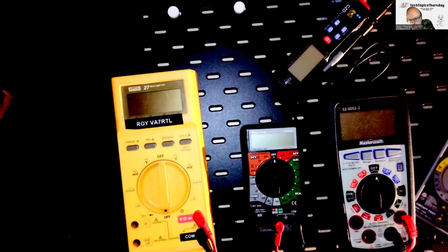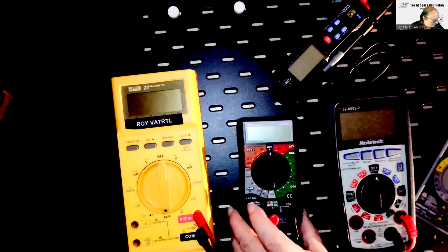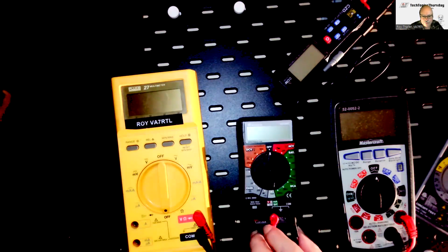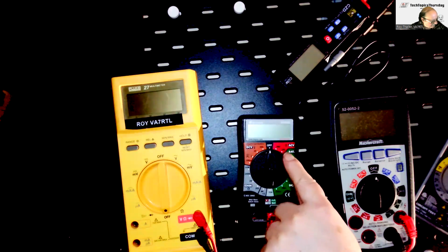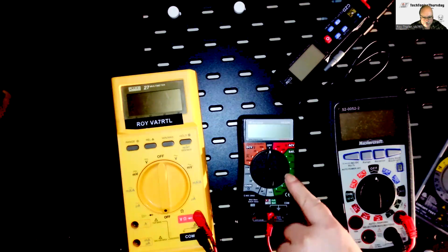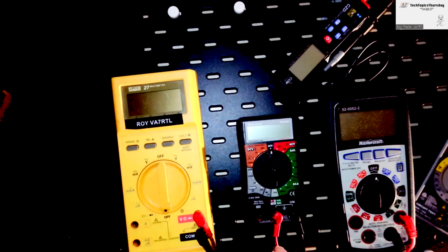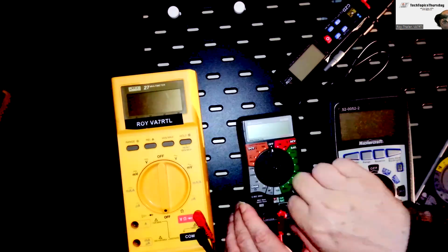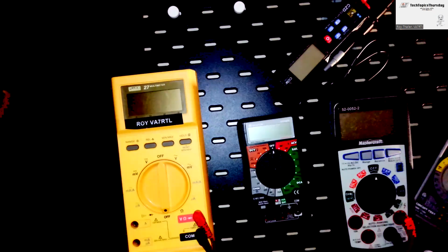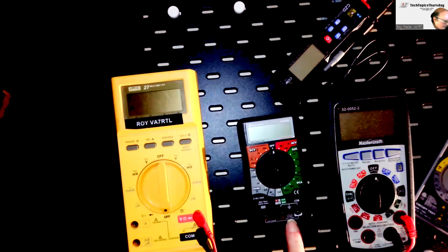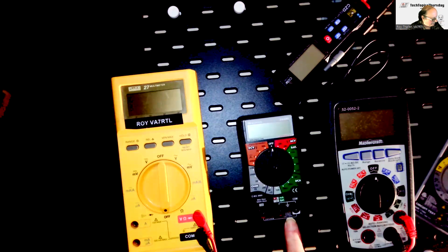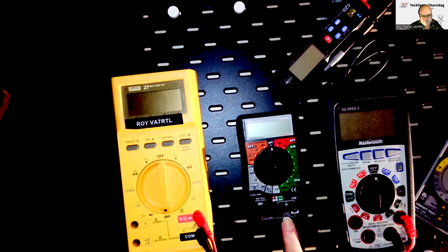This meter I got at Canadian Tire, probably because it has the battery scale here to measure batteries. But when I look at the rating, it says Cat 1, which is the least amount of protection, and 500 volts. So do I really want to use this meter at 500 volts if it's Cat 1 rating? Probably not. It's also fused with a 315 milliamp fuse.